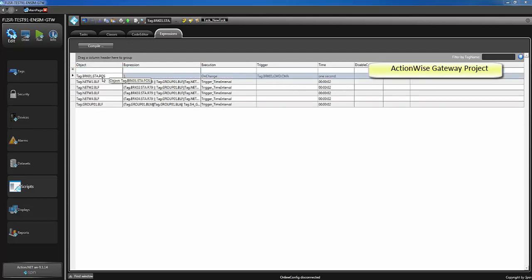For example, for the first breaker, use its status breaker position tag, then use an expression for it, and select On Change for execution mode. You should refer to the command tag for opening the breaker. Then, repeat the same model to refer to the command tag for closing the breaker.